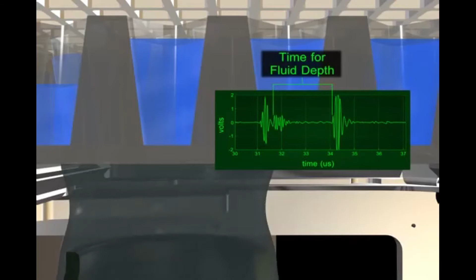The information provided by the survey determines that the proper ejection parameters and transducer positioning are used to ensure accurate and precise nanoliter transfers. The actual total analysis time for a 384 well plate is less than 26 seconds. Once the wells have been surveyed, the transducer returns to the first well, focuses the acoustic energy where the survey determined the meniscus to be, and emits a stronger ping of energy.